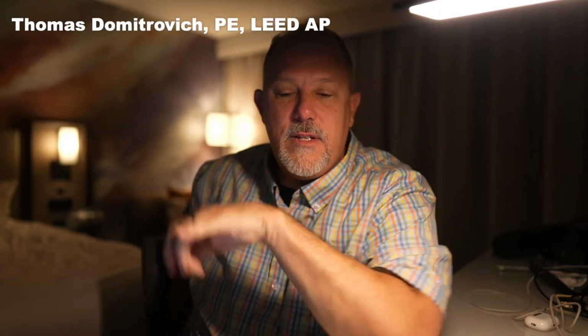210.8F is where it's at. What did we do on 210.8F? We removed that effective date language. We had a correlating committee note that said you have this thing that says effective September 1st, 2026, GFCI or SP GFCI protection shall be provided for listed HVAC equipment.